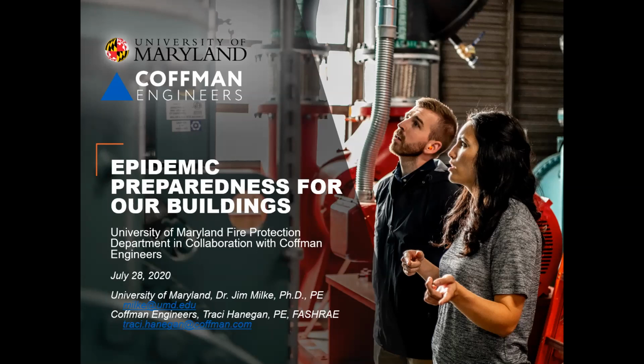When we think about existing buildings and retrofitting, a lot of buildings don't operate as well as they were intended to when originally designed. We have things like coils that get fouling over time, so we don't get as much heat transfer through them as was originally designed into the system. So we can go in and retro-commission facilities, look at them and say, here are some things we can do, maybe with the control system and how things are sequenced. Maybe we change out some coils for ones in better condition, and build a little extra capacity into it at that time.